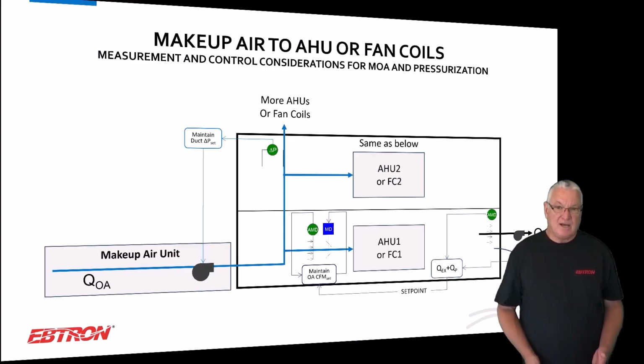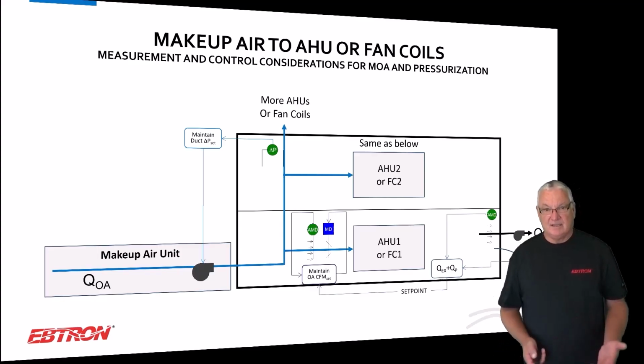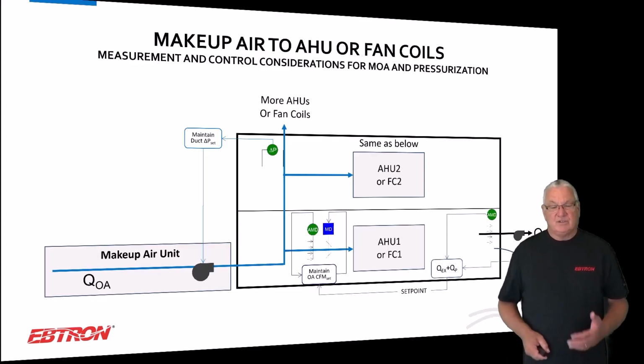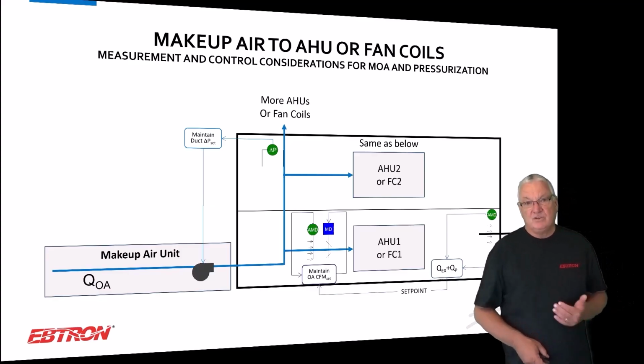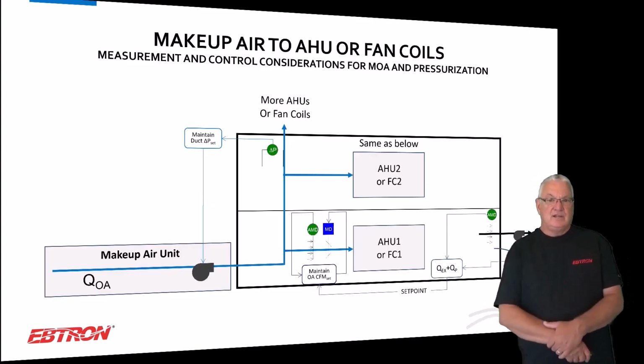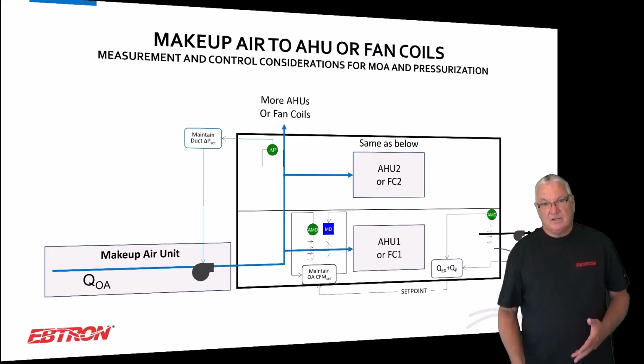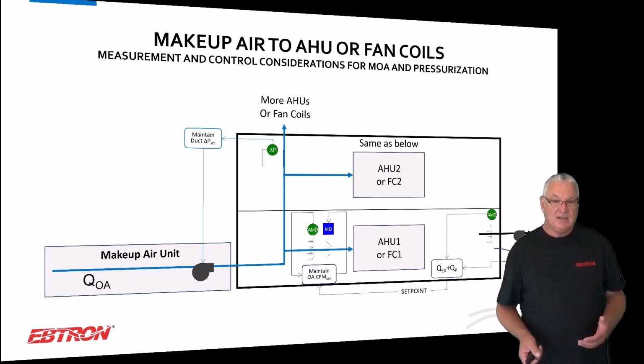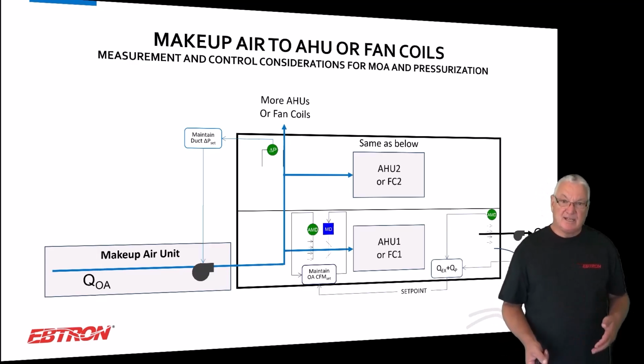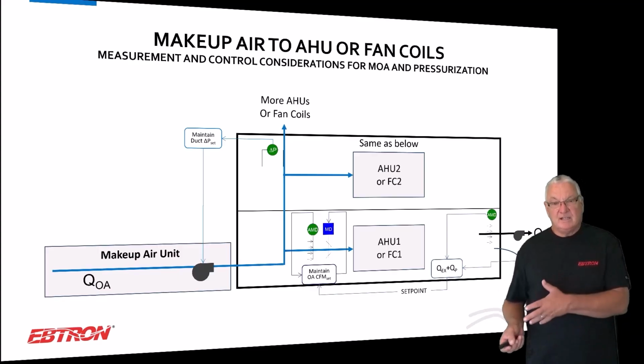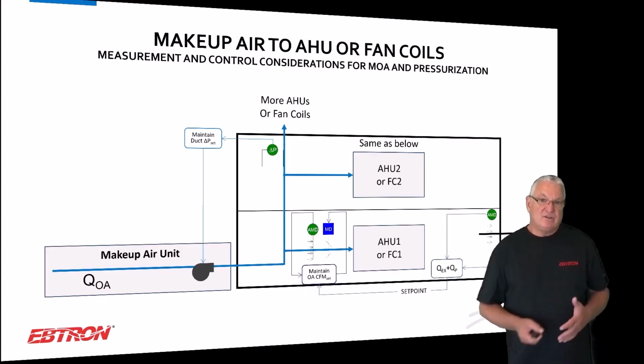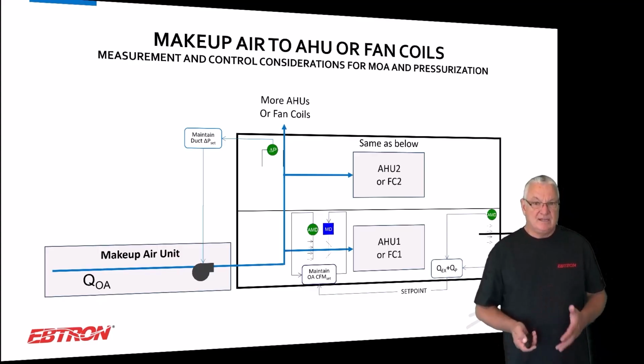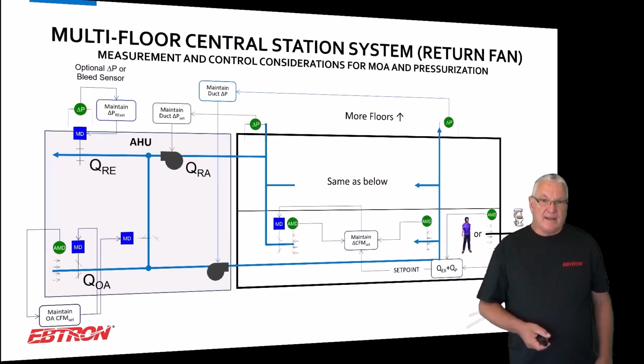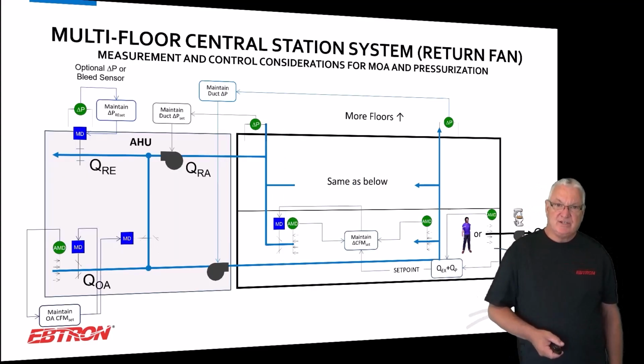But the bottom line here is, let's say this was multi-floor. If you don't do the differential on a multi-floor building, then you have to deal with stack pressure issues. If these are fan coils and the outside air to these fan coils is changing, maybe based on DCV or something like that, then it's changing the flow into all the other fan coils. So yes, you should measure and control to keep your set point for each one of the fan coils. Okay, multi-floor central station systems.